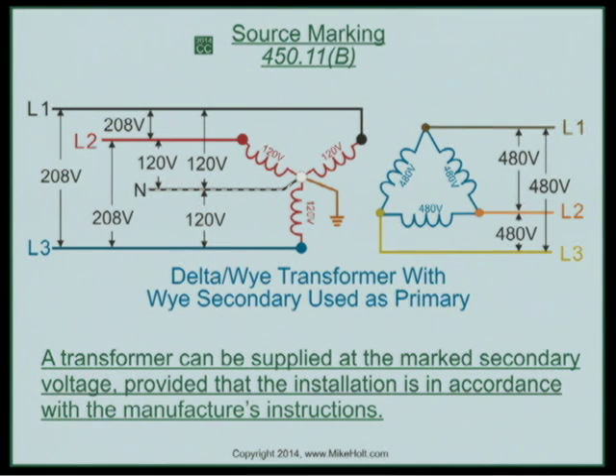Okay, my recommendation is before you just go ahead and do this, you have to understand that here we have a standard transformer, and you just mentioned that they're going to need to purchase a ground detector for the ungrounded system. You can buy a step-up transformer from a manufacturer, and chances are the price of a step-up transformer might be cheaper than a standard transformer and a ground detector. Without a doubt, the best thing would be to know in advance what you need. Get a transformer that's going to be a 120/208, 480 volt, specifically for this application.